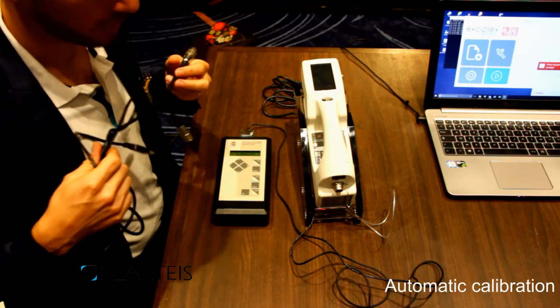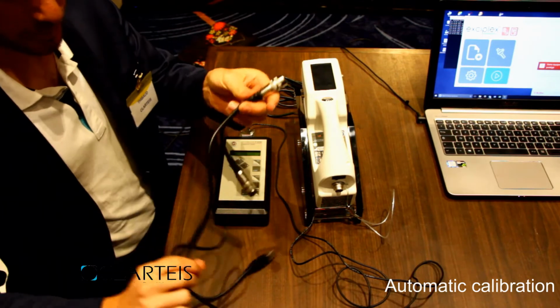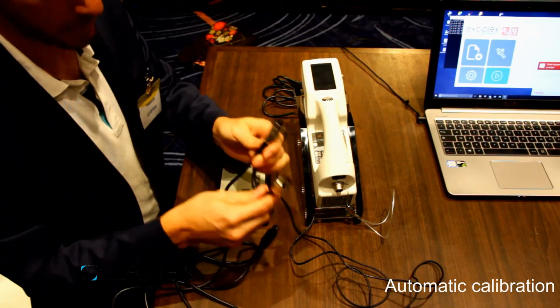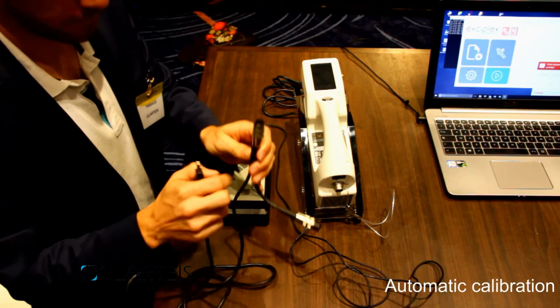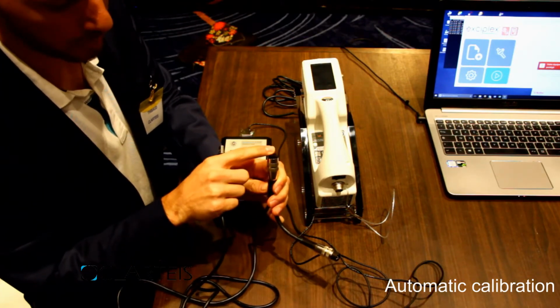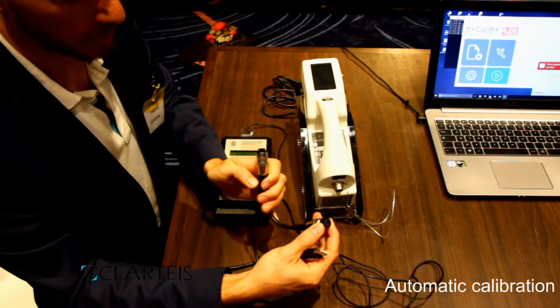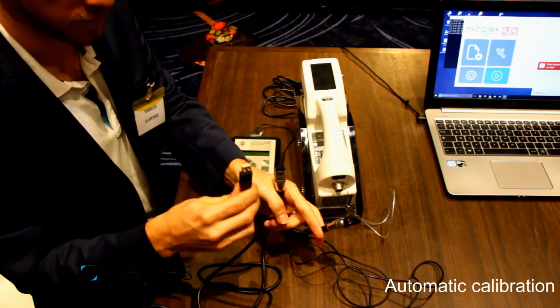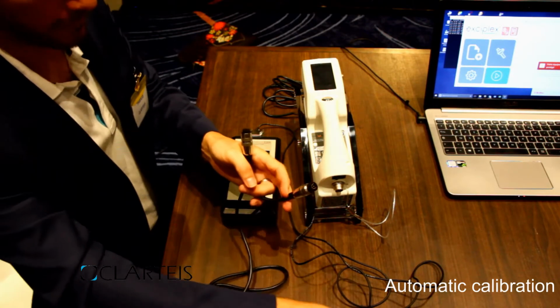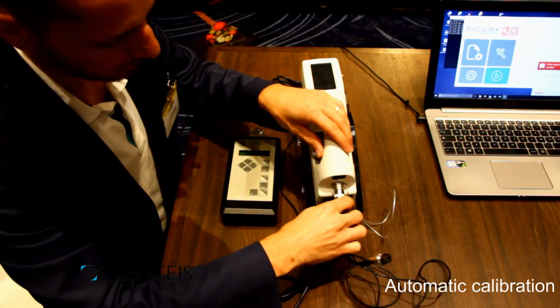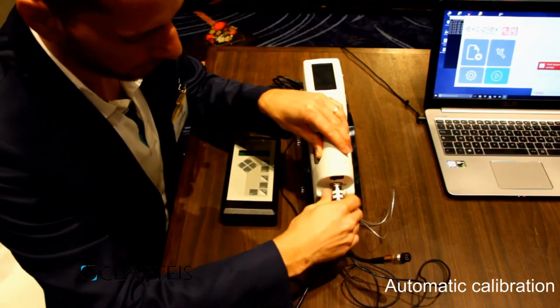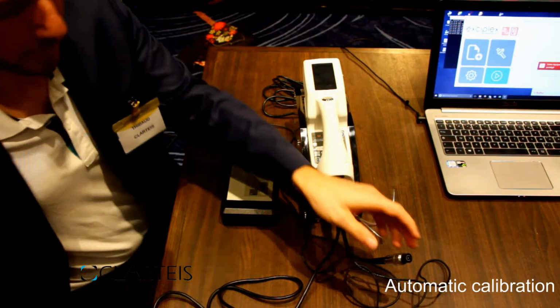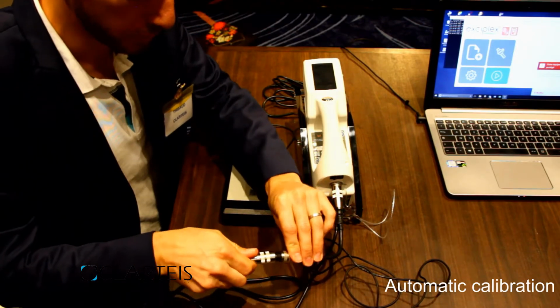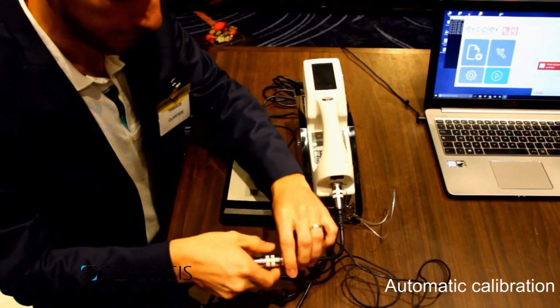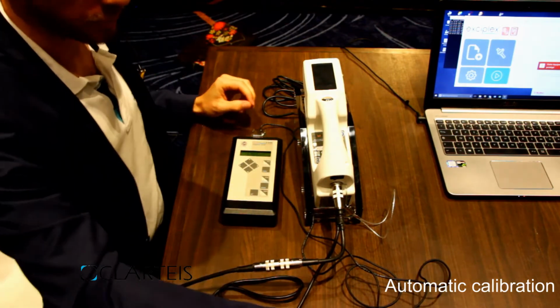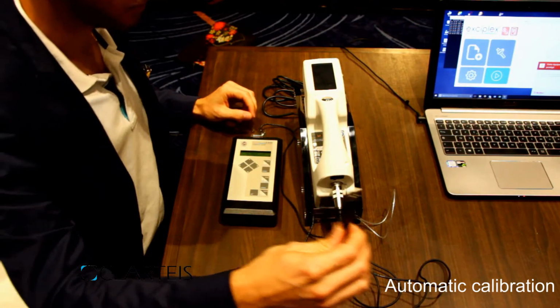In order to perform an automatic calibration, you will need a Y cable provided by Clarteis. So it's an input connector with power and communication. This one is only power, and this one has to be connected with your computer. So first, connect the power cable to the Y cable, and you can connect this connector to your PC.